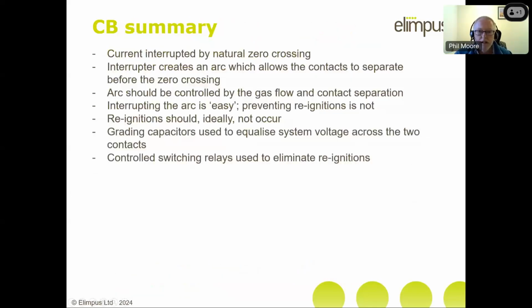So just a little bit of a summary there. I'm sure you all know this, but I'll repeat it anyway. In a circuit breaker, we interrupt the current by using a natural zero crossing. The interrupter creates an arc which allows the contacts to get far apart before the arc goes out due to the zero crossing, which then provides the dielectric withstand voltage. You control the arc by the gas flow and the contact separation. Interrupting the arc generally is easy, but preventing it reigniting isn't. That's the difficult thing.